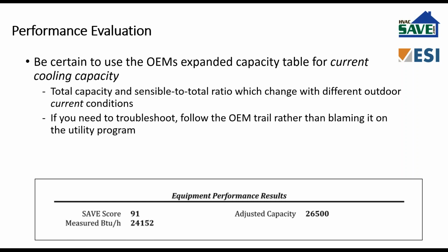At this point, it's not the AHRI lab. And the OEM does not know what time of year that equipment is getting installed, or whether it's Des Moines or the Quad Cities or Honolulu or Miami or Austin. That is the purpose of them providing you those performance tables, those expanded capacity tables, all right? They're also used for design considerations.